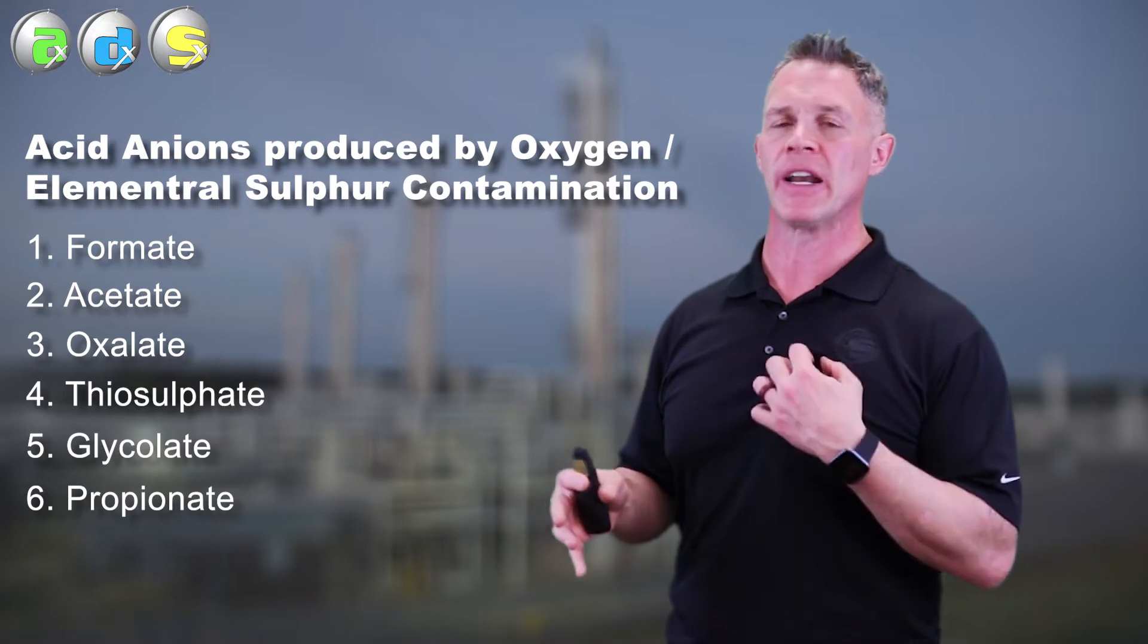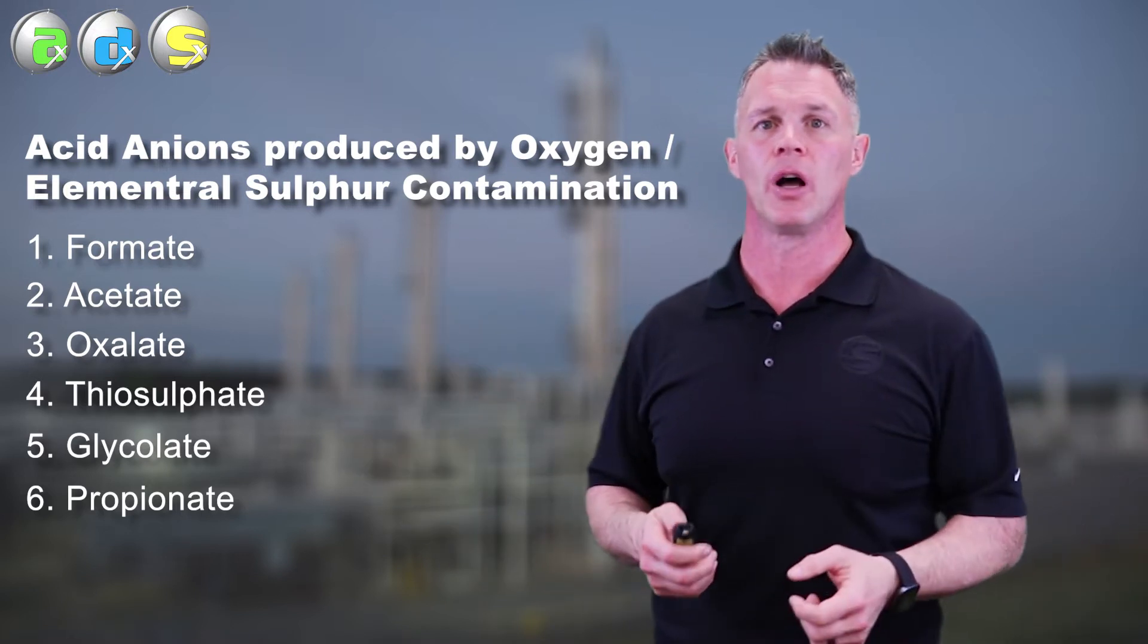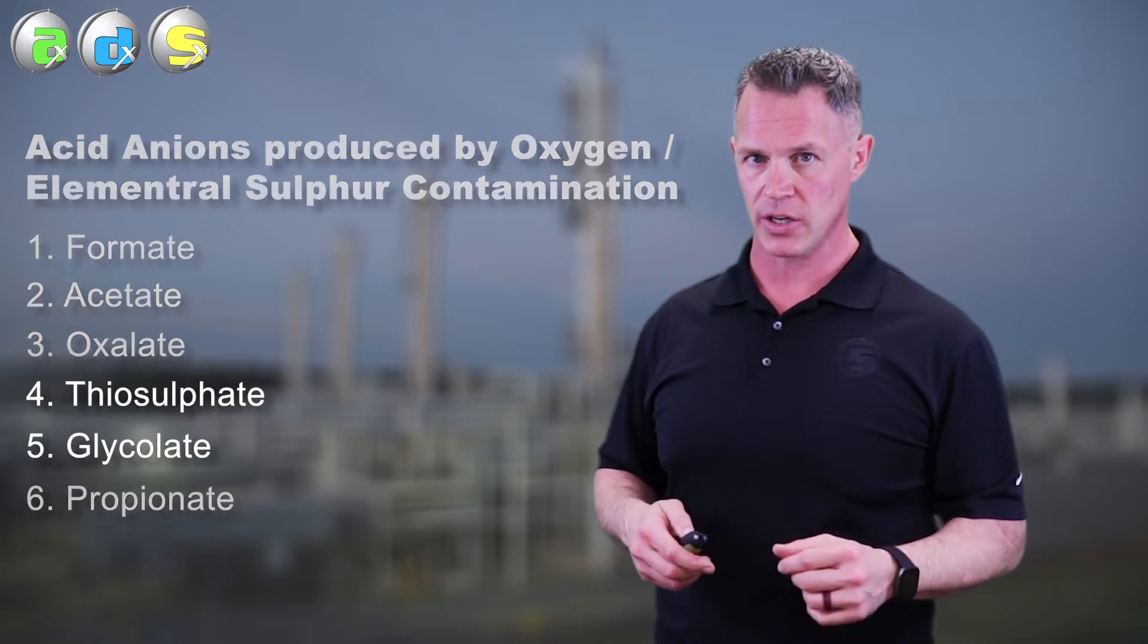Elemental sulfur is a little bit easier to identify because you'll see it in your amine filters. It's a physical solid, so it plugs stuff off as well as causes these reactions.